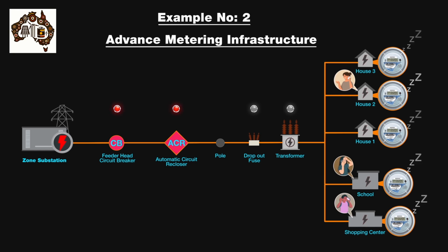The OMS then analyzes the network hierarchy, mapping which meters are connected to which distribution transformers. It aggregates the last-gasp signals from individual meters to identify a single event per transformer. This method equips the DNSP with real-time insights into the scale and specifics of the outage, eliminating the need to rely on customer calls. Consequently, the DNSP can proactively initiate broadcasting outage information to customers and expedite the restoration process without delay.